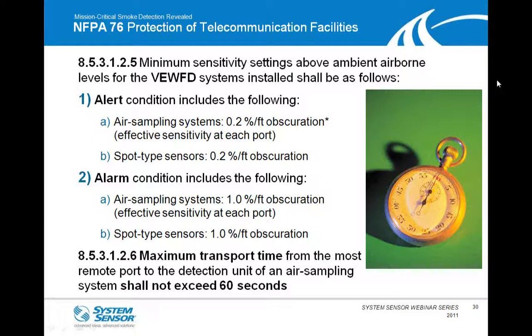Let's say you have an air sampling system that has 10 holes. Only one of the holes might be detecting the incipient stage of a fire. So that one sample gets diluted by the 9 other samples when it gets back to the device. So the device has to be set significantly more sensitive to meet that 0.2% per foot obscuration. Similarly, an alarm condition, whether it's air sampling or spot detectors, needs to be at 1% per foot obscuration. And finally, if you're using aspiration systems, it calls out that the maximum transport time cannot exceed 60 seconds. With aspiration systems, there is a transport time between the time smoke is introduced at the sampling point and the time the device detects that condition. For very early warning, it has to be 60 seconds or less to meet the standard.